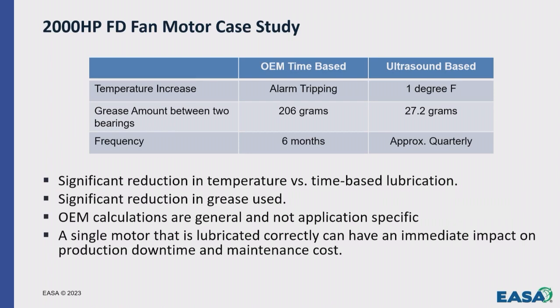Good opportunity right here. Our customer knew that we were doing ultrasonic lubrication. They called us up. They were having a problem with a 2,000 horsepower FD fan motor. Large motor, critical motor, very large TEFC motor, so it has large bearings, very special considerations. And they were going time-based. They were going based on what the OEM was telling them to put into it. That was 206 grams split between both bearings every 6 months.